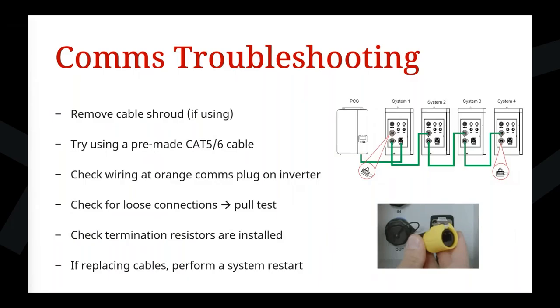Some other things that you can check or do. If you're using one of those cable shrouds as shown below, try removing the cable shroud, connect it again, and see how it goes. Just note, those cable shrouds are not necessary if you're doing indoor installations. Another thing you can do is try a pre-made Cat5/6 cable, which I said before. You can check the wiring at the orange communication plug on the inverter and make sure that's all correct. You can check for any loose connections, so try doing a pull test. Check if the termination resistors have been installed.